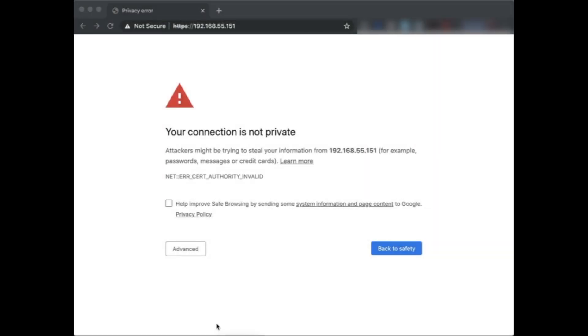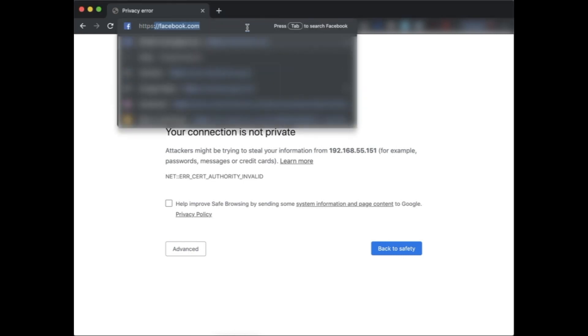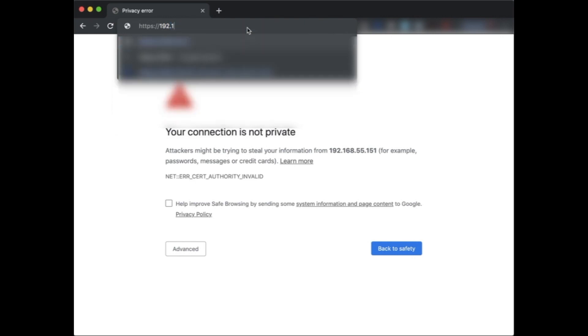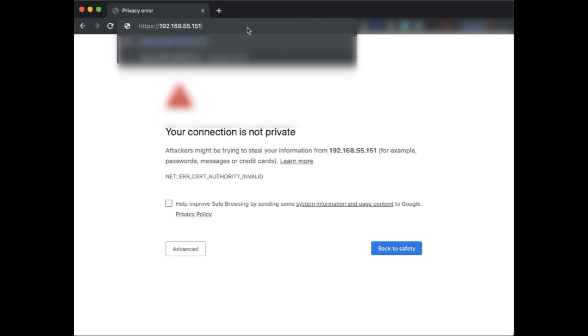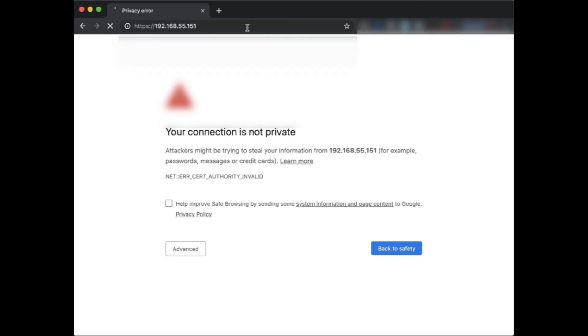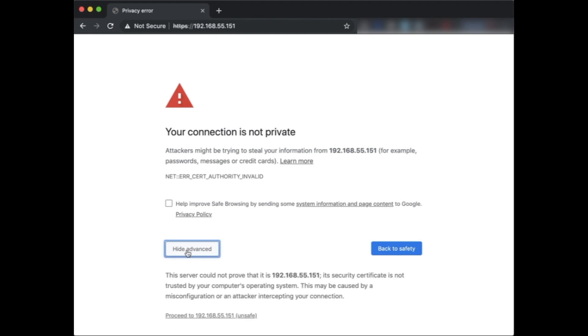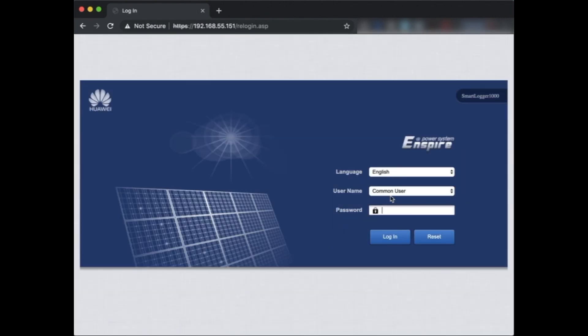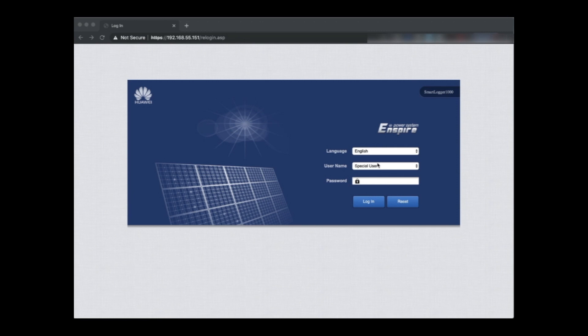First you need to log in. Make sure that you put the https colon slash slash in front of the IP address of the smart logger. So remember to check the smart logger's comms parameters to find out what its IP address is. Now depending on what browser you're using you might get a security alert because there's no SSL certificate being supplied with the unit. That's not a problem. You're local. It's not the internet.